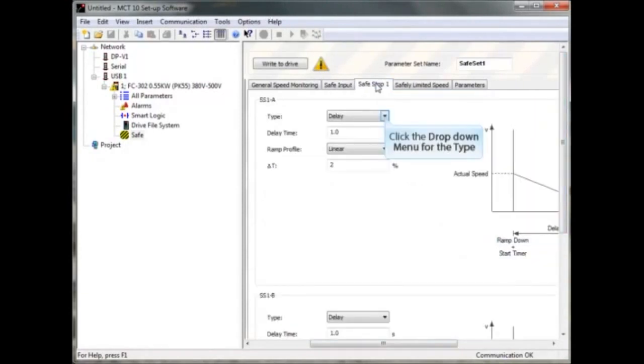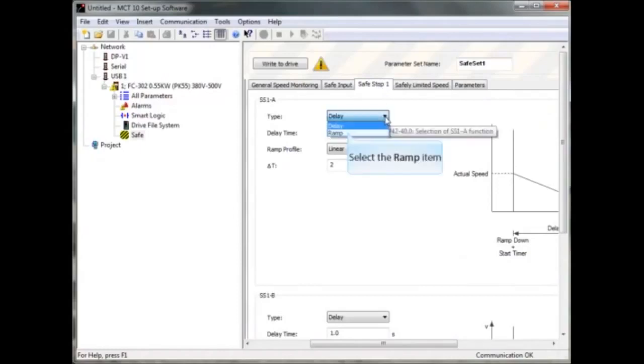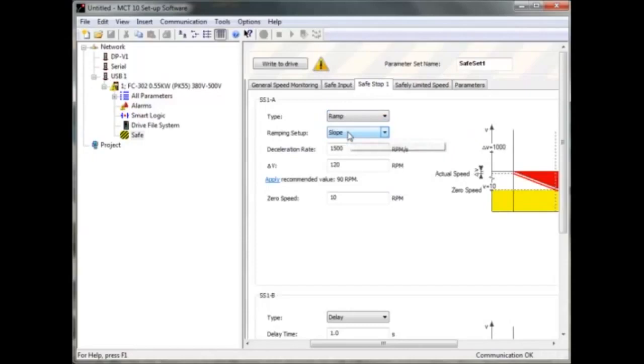In the next sheet you choose the SS1 settings. You can use a controlled ramp on the MCB150, or just do a delay with a time, which is also what the MCB140 does. With a ramp, you can run it with a slope — meaning how many RPM per second it should ramp down. Or just with a time, meaning in how many seconds it should ramp down.